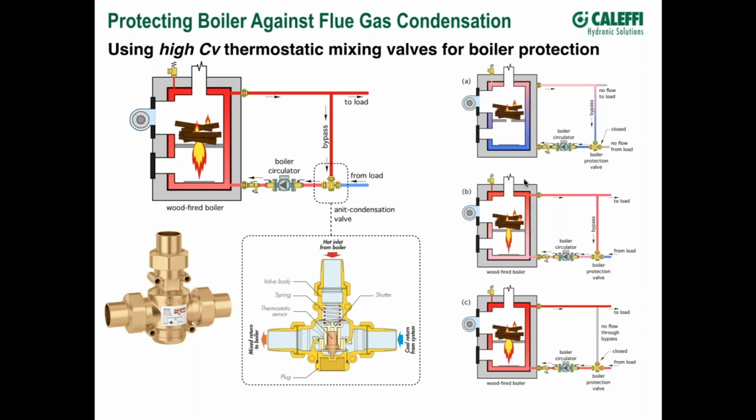So if you add the 18 degree, what was happening is my boiler has a variable speed inducer motor like you see on that one there, and my boiler was starting to ramp down its output before the valve got to that 18 degree plus the 130. So I was starting to lose my full output of the boiler. So I went down to a lower size, went to the 115 plus the 18 degree differential, which got me pretty close to the protection I wanted. So that's why, when you buy one of those, know that they will have a couple choices in the sensor that you can put in it to fine tune them to what your application is.